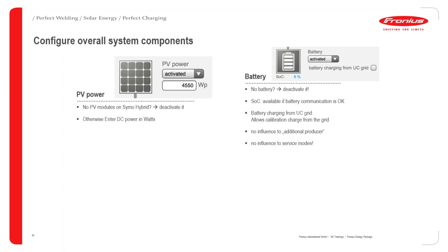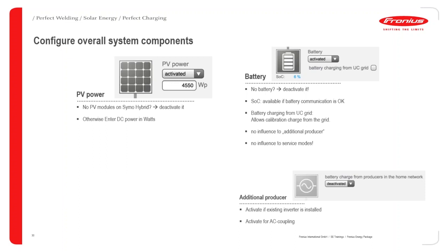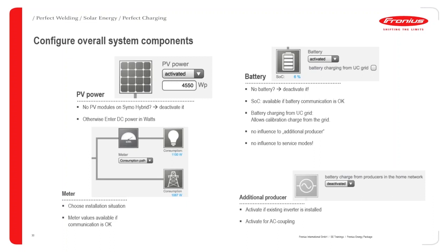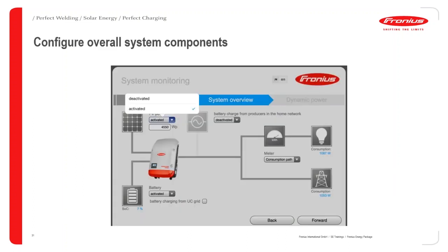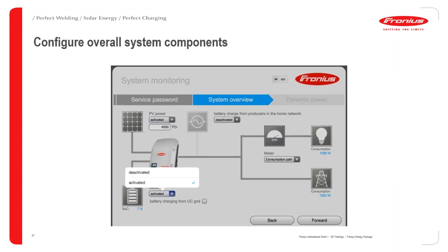That doesn't change how the service modes are, or any other additional AC sources there. You've also got battery charging from UC grid, so they're talking about utility company grid is the name for that. So if you want to do that, what that does is it allows the calibration charge, which gets done every now and then. There's a lot of different factors that depend on when that happens. So it could be once a month, could be once every 2 months. It just depends on how the battery is getting used, if it's being discharged or charged completely. That's a fully automatic function, and the calibration charge means that it charges right up to 100%, so that all the measurements and all the internal measuring equipment and devices are calibrated every now and then to give the correct readings.